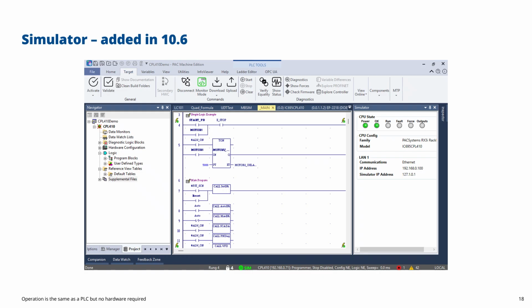The benefit of using the simulator is, of course, you don't need your hardware, but also it allows you to try things out before you actually connect to the physical device. It's a great way of making sure that any logic changes you're going to do will work. Whenever you do an online change, you might change the logic in a way that is valid for download, but that stops the machine from operating. So the simulator is a great way of testing things out before you get to the physical machine.